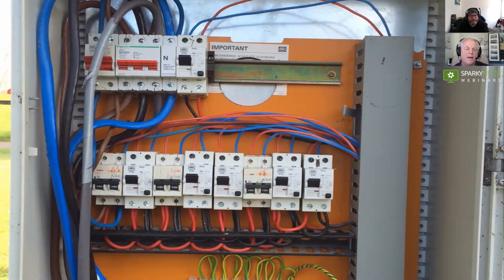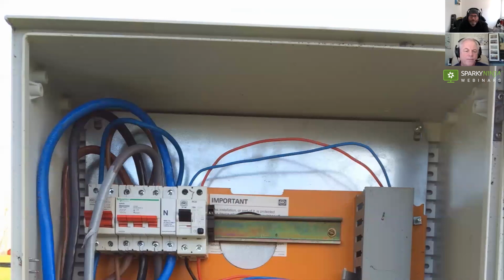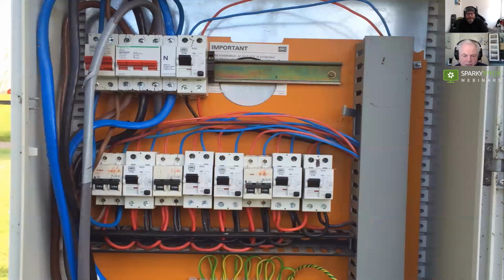That top one there, which is those cables there again, they're not protected, are they? Because that's just an RCD. Just an RCD. And I think that's fed off of that. If you look at the loops at the bottom. Yeah, it's off the loops. It's coming off of the bottom of that right-hand one into there. Basically, they've run out of space, so they went up here to carry on. It's come out of that right-hand side one, up over to the top, and then to that RCD, and then away to another circuit. So again, there's no overcurrent protection on that.